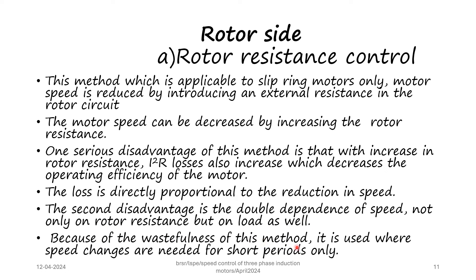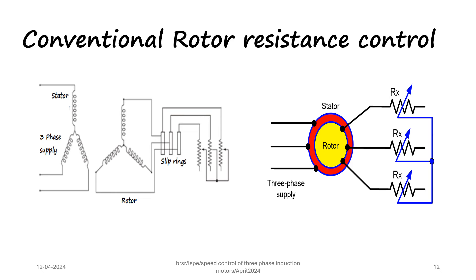Because of the wastefulness of this method, it is used only where speed changes are needed for short periods. Rotor resistance control can be achieved in the conventional way or the static way. In the conventional method, the slip rings are externally connected to a rheostat. By adjusting the resistance of this variable rheostat, the net rotor resistance is increased, thereby changing the motor speed.